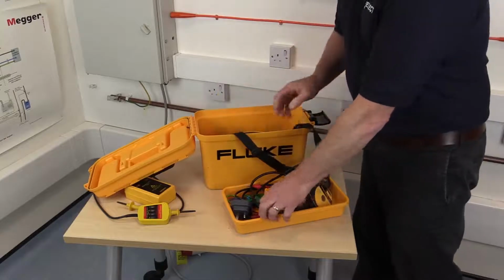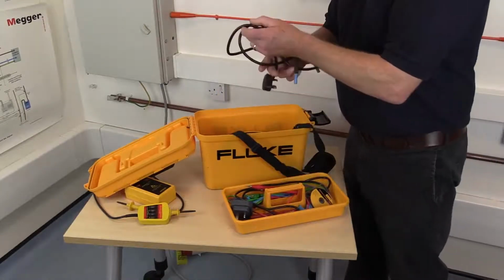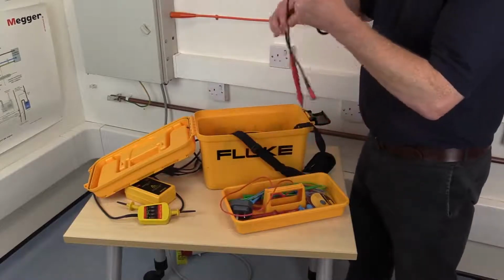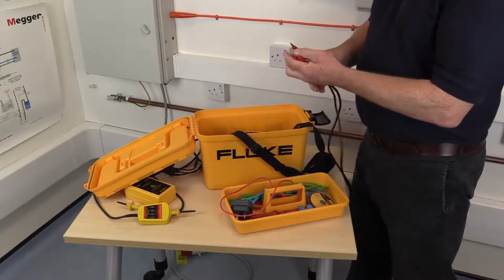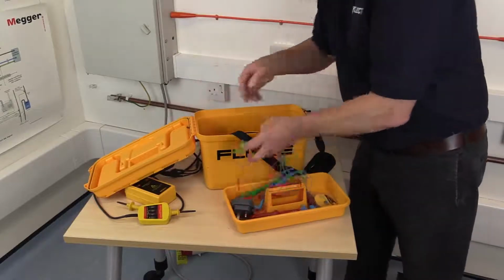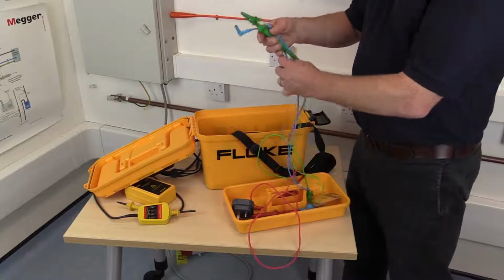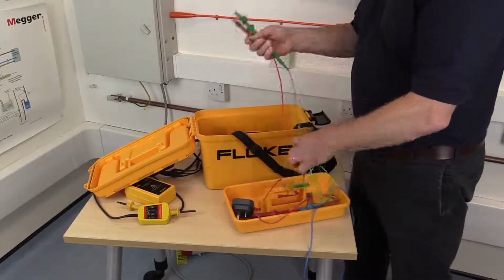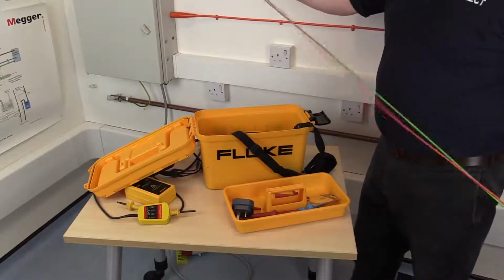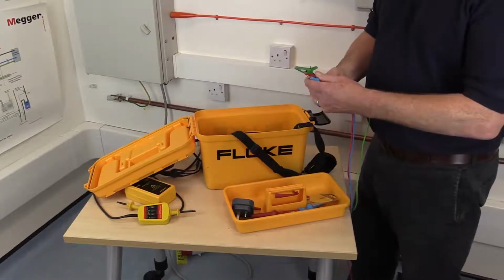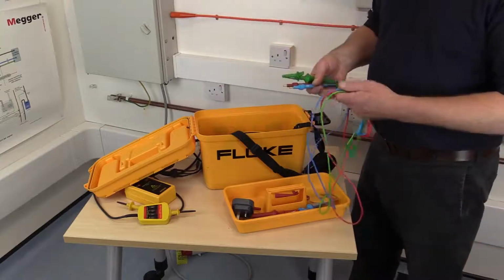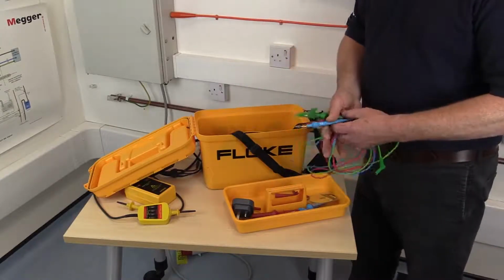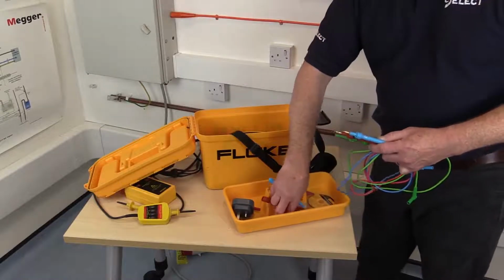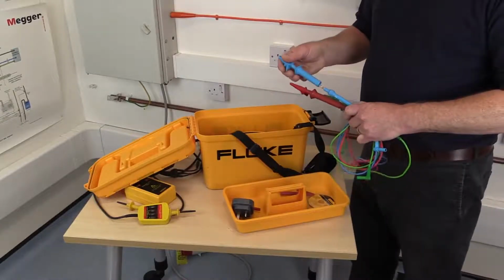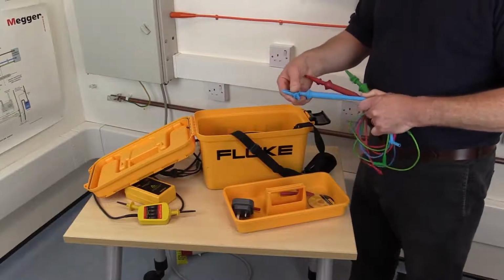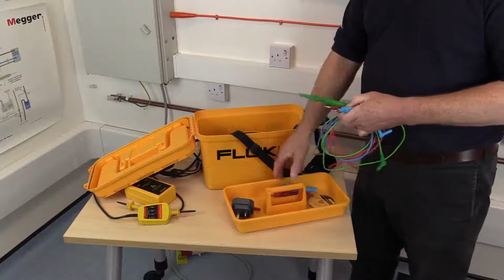It should be regularly checked and maintained where required, and its accuracy confirmed by calibration if necessary, and this is recommended. It should be ensured that test leads to be used are compatible with the equipment. And remember, different manufacturers may have particular requirements. And the test leads must be in good condition and suitable for the range of test voltages and currents applied. A suitable range of probes and clips should also be available as necessary to carry out specific tests. For example, fused probes compliant with HSE guidance may be necessary for undertaking any live tests.